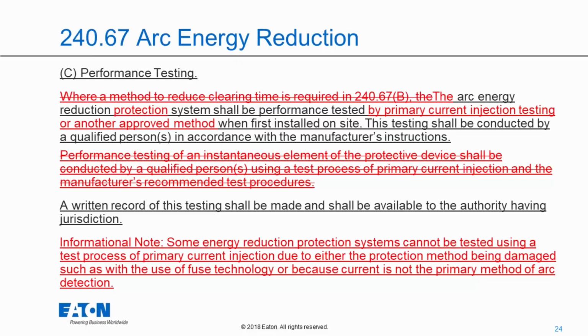No matter what type of technology you use, do definitely consult the manufacturer. The manufacturer will have, at least I can speak for Eaton, very detailed instructions on exactly step by step how to do the testing of the technology that you selected. And again, make sure that's a qualified person doing the testing. You know, if you have a person who typically does only residential electrical work, you probably don't want him doing this type of testing in a commercial or industrial facility. He probably is not qualified to do that testing. They also want to make sure that a written record of the testing shall be made and shall be available to the authority having jurisdiction.